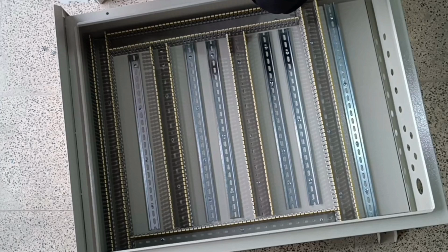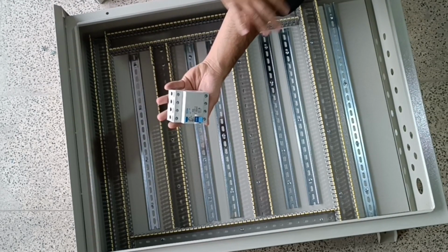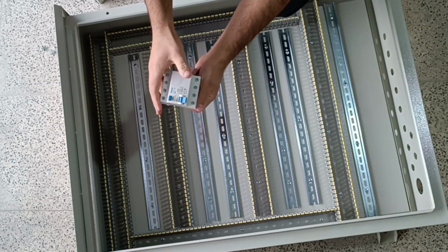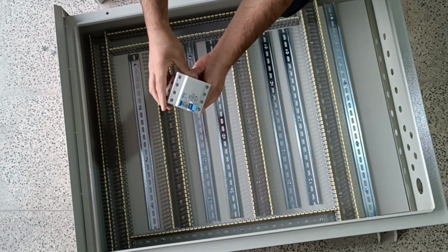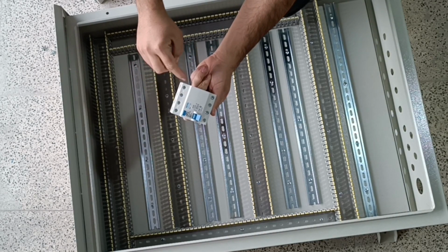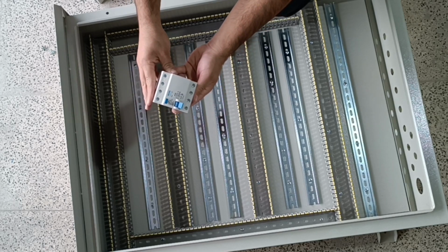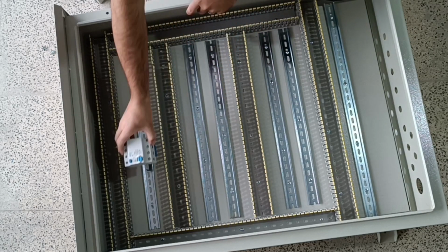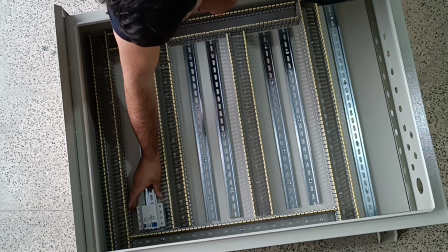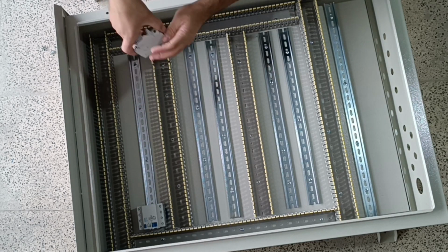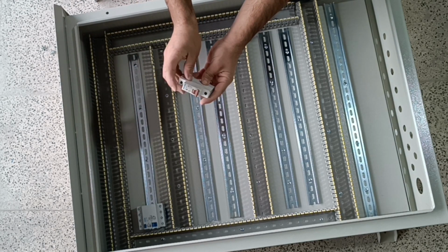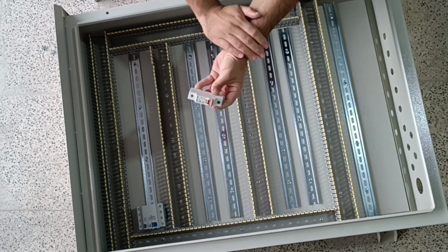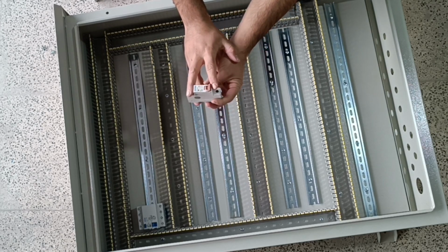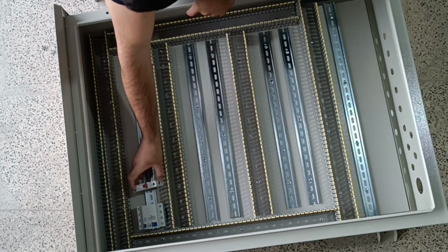Now we install the equipment in the electrical panel. As the first device, we use a 3-phase RCCB switch. This switch provides power to the entire electrical panel and is used as the main switch. This switch protects the circuit against current leakage and electric shock. This is a single-phase miniature switch that is used to protect the control circuit against short circuit. These switches mainly have a low current limit.